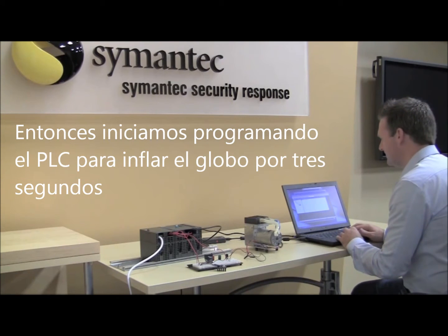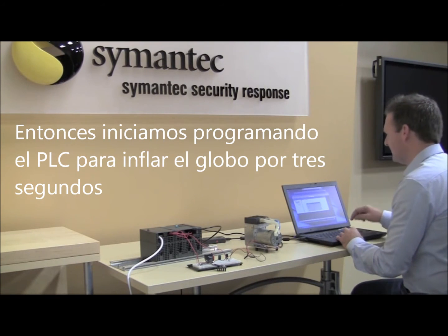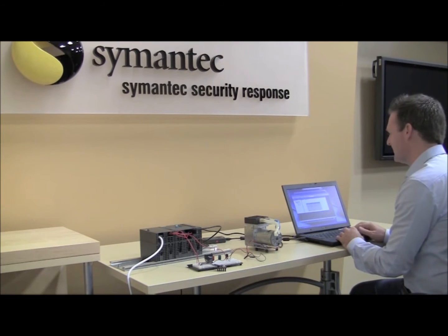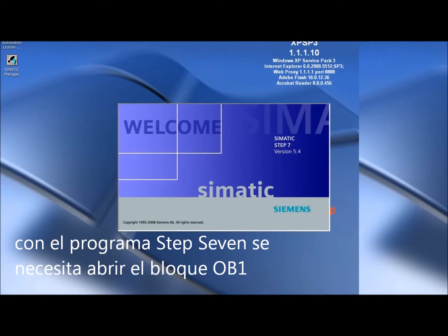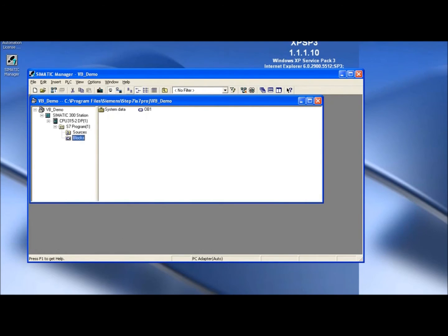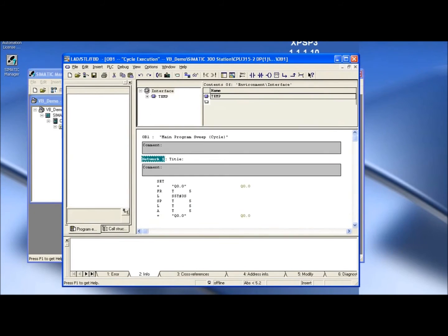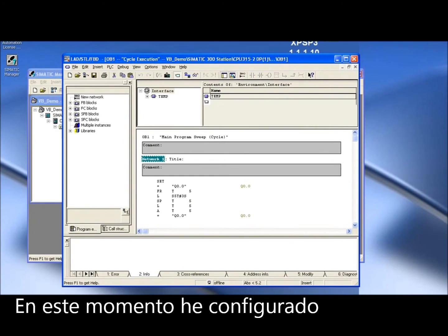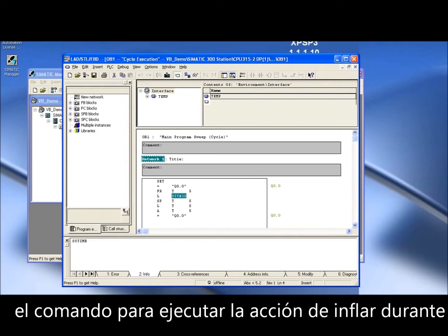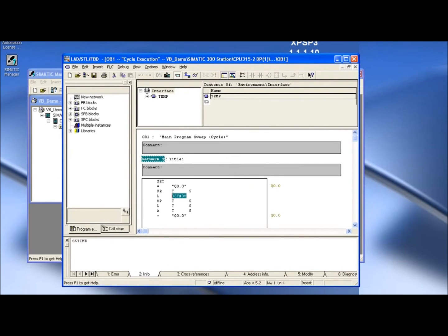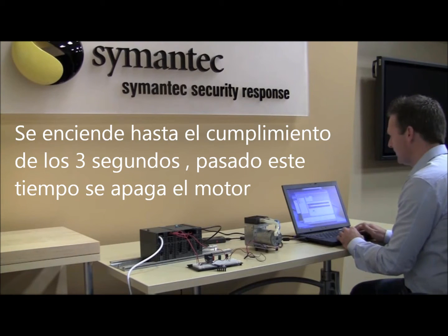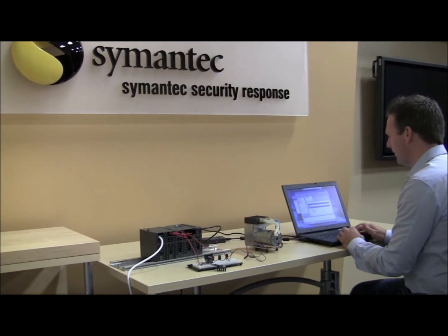To program the initial PLC to inflate the balloon for three seconds, I use the software Step 7. In Step 7, you need to open up the code block OB1. Inside code block OB1, I have this timer set for three seconds — 3S is the important command here. This timer is going to run for three seconds, turning the pump on until the timer is finished, and when the timer is finished, it'll turn the pump off.